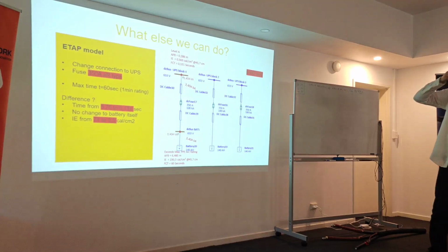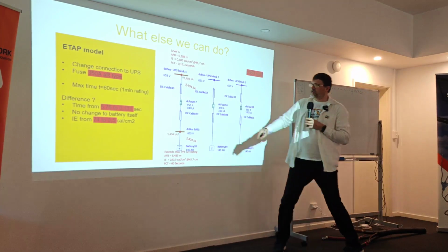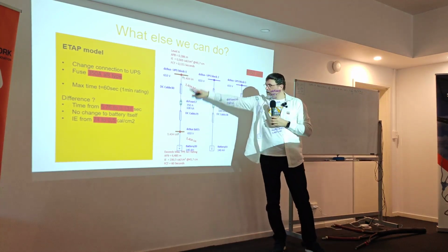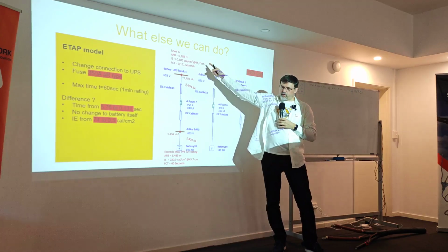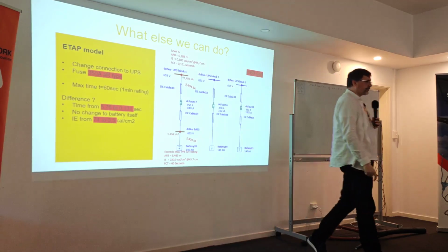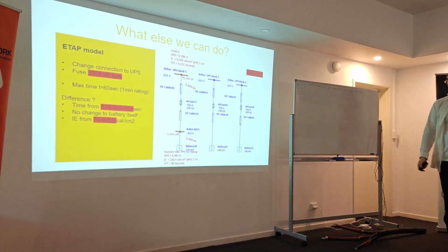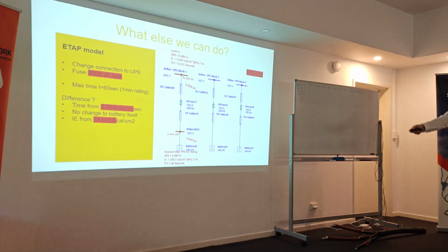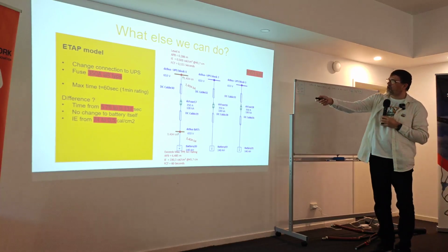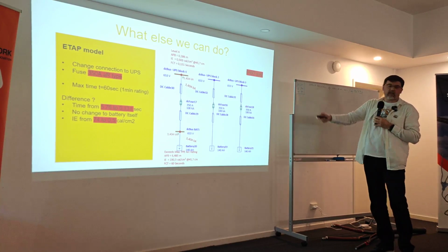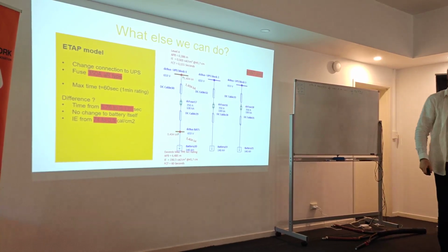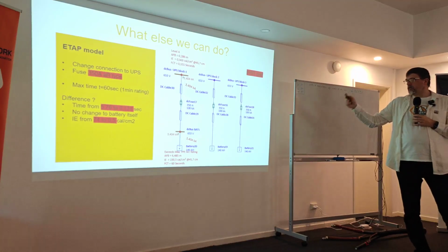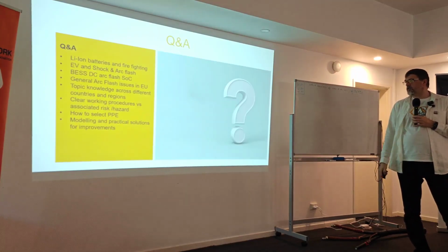And what else you can do, which will happen sometimes on different UPS, but this is not a solution, this is more like choosing the UPS later. Instead of having 3 strings per core, you can have 3 strings per 3 cores, and adjust a little bit differently. This will just limit the amount of energy accumulating from the others. So it goes directly, not to the common bus, but each specific core gets their own battery rack, let's say. It depends how they design it; sometimes you can just design one line, a common bus, everything connected to it, but it's also accumulating at this bus at the end. And you might not have to do it. So that gives a bit of change.